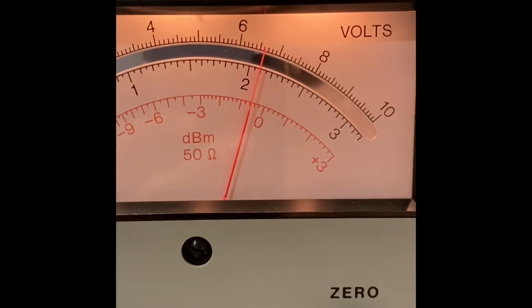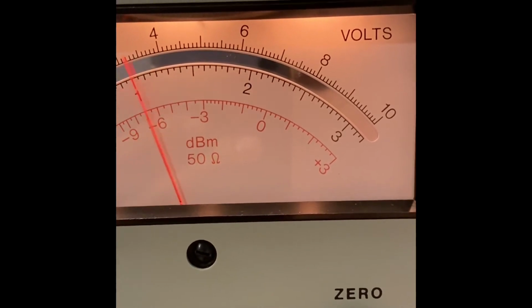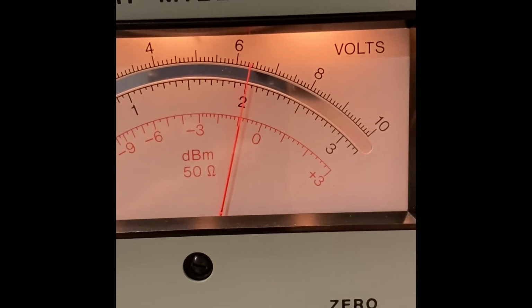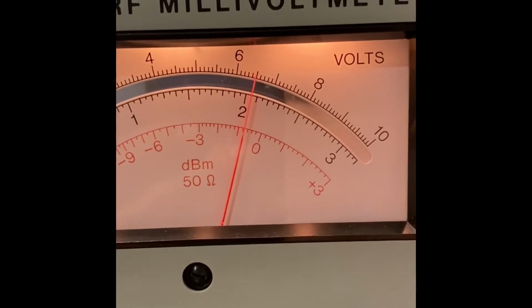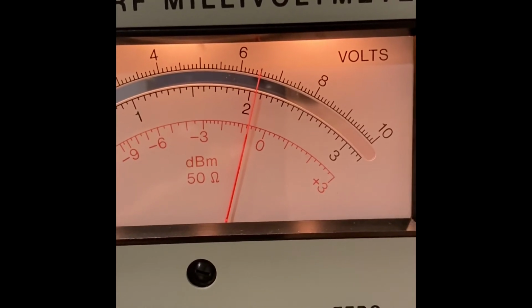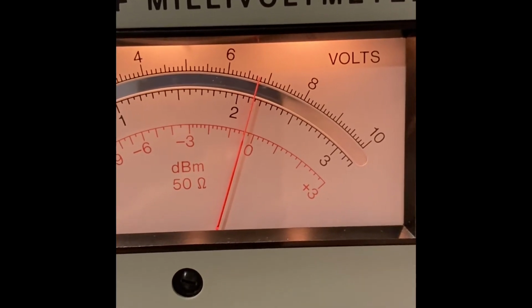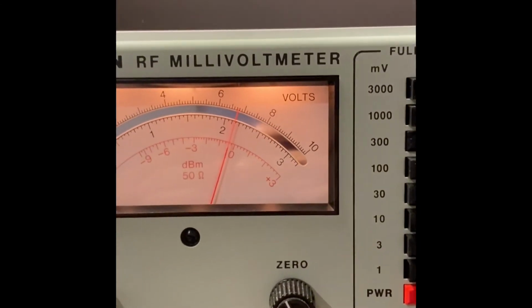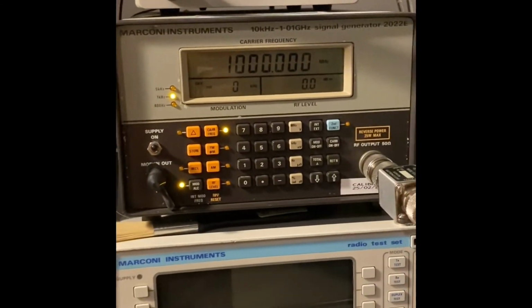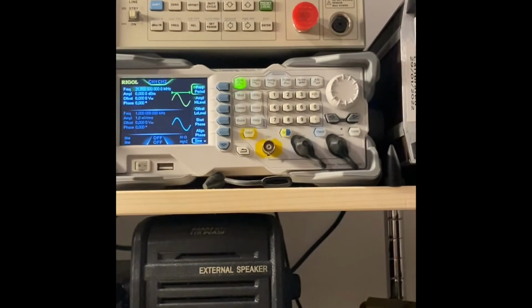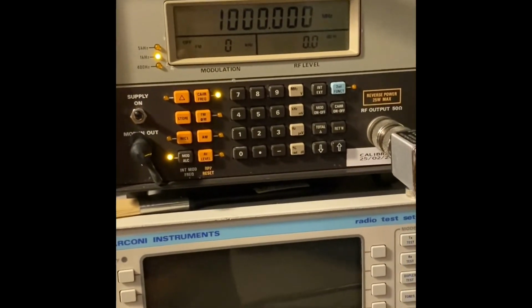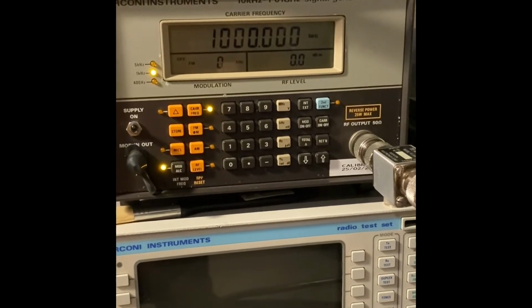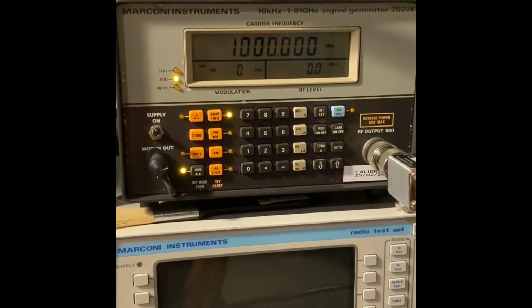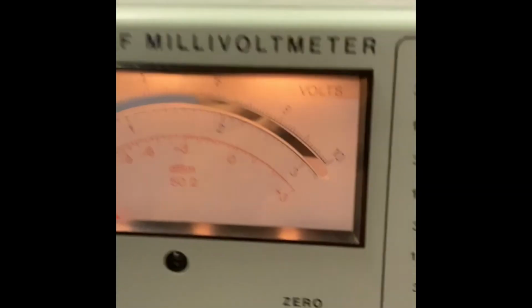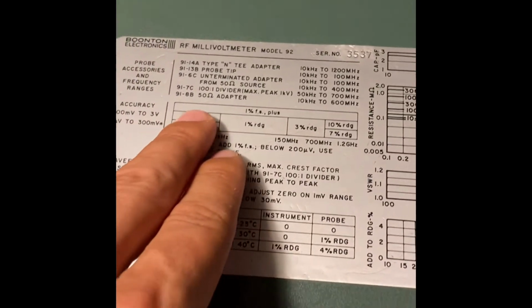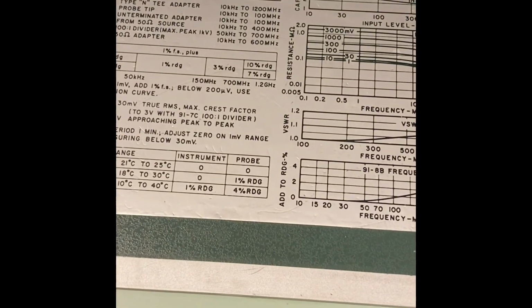That's 0.5, almost 0.6 less. 300 megs. It's going a bit down. 400, 500, 600, 700, 800, 900, 1 gig. Now, obviously, there are a sum of errors. One is from the voltmeter, one is from the Marconi. Obviously, the RF power meter, which I use to calibrate the Marconi, has some errors as well. So, yeah, I would say that's a good result. And in fact, if you notice up here, there's a table which gives you all the informations for the accuracy.